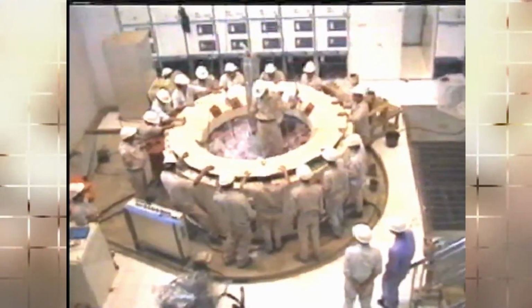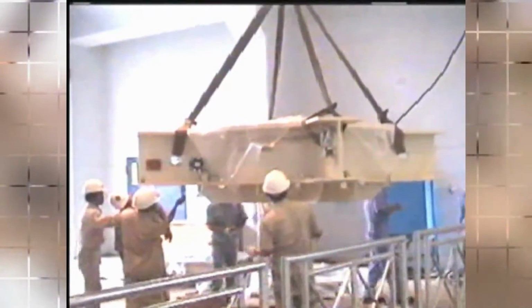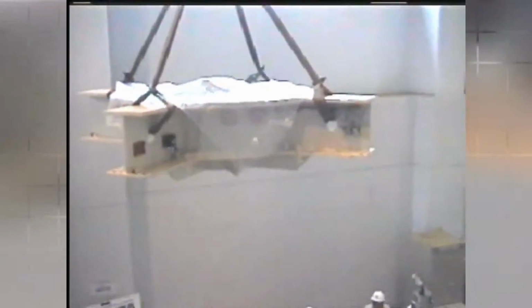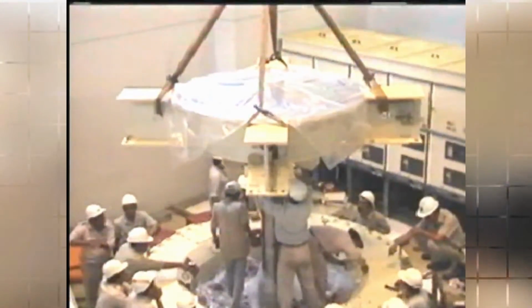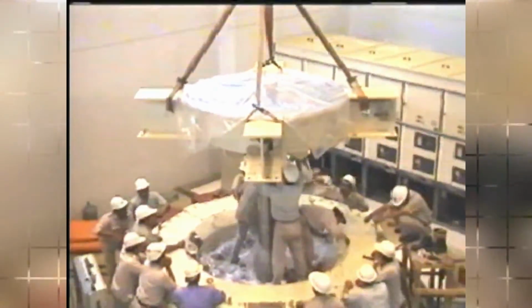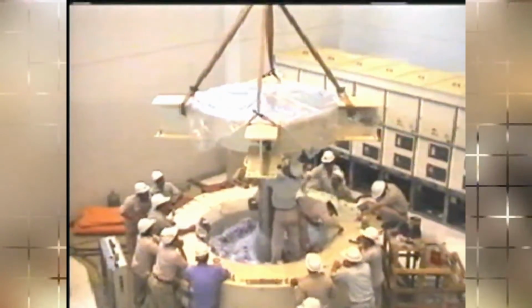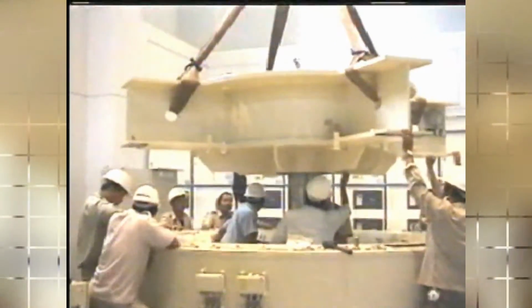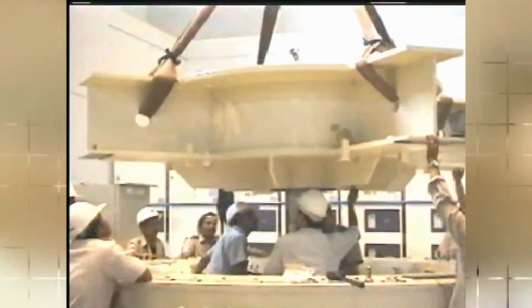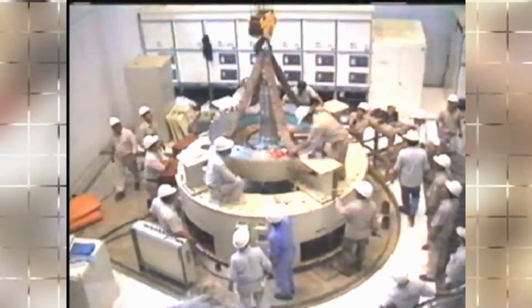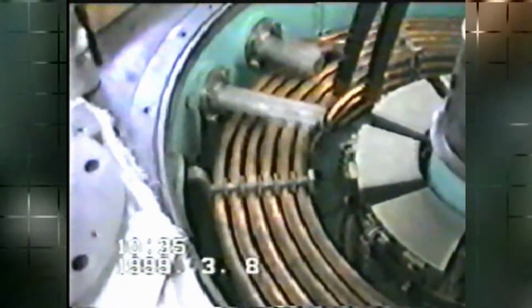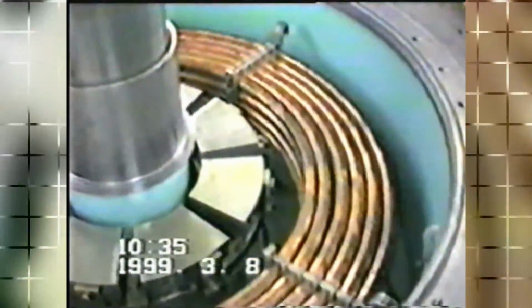The brushless excitation system is installed for the generator. The brushless excitation system consists of an alternating current exciter or AC exciter, rotating rectifiers, excitation transformer, field switch, voltage regulating equipment, and other accessories. The AC exciter is designed to withstand the maximum runaway speed of the turbine for 5 minutes without damage.